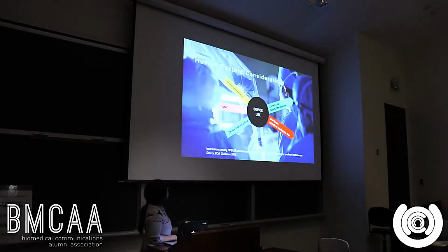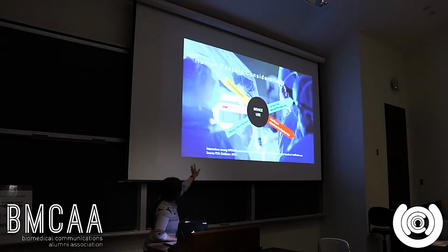So why is there such a huge emphasis on the human factors approach to design and development for medical devices? It's because what we usually have control over is the UI and the device, but what we don't have control over is sometimes the user and the user environment. And that's what we have to consider a lot of times. That's where following the previous standards comes into play. So for us designers, it's good to refer to those standards to help inform us on best practices to avoid any use errors that might lead to unsafe or critical situations.